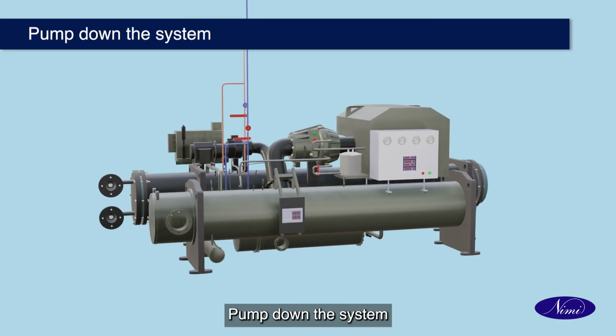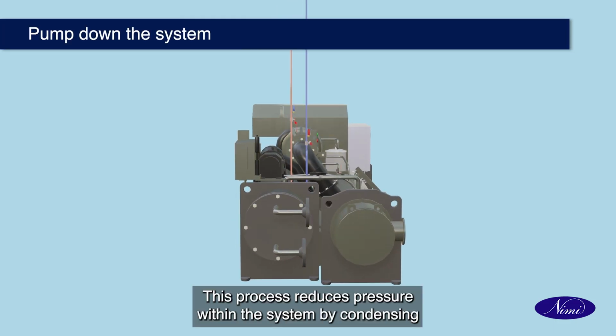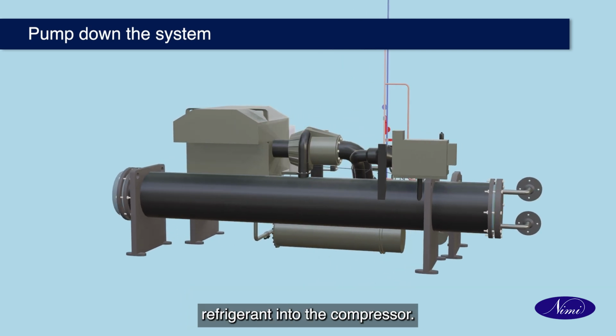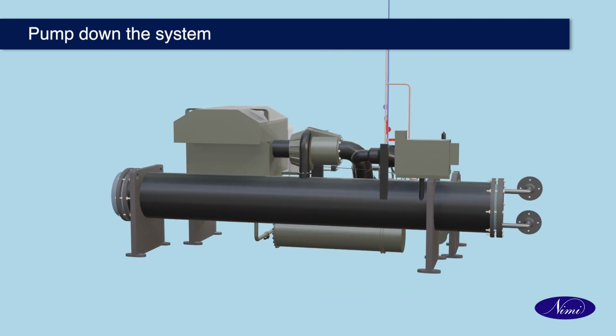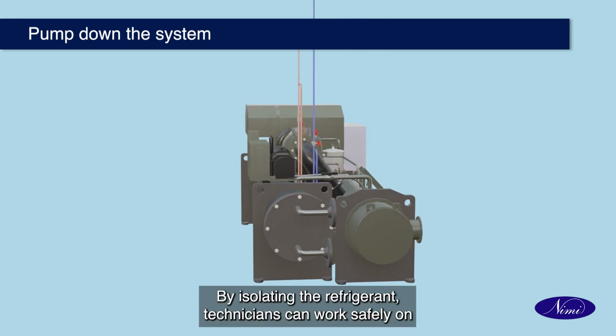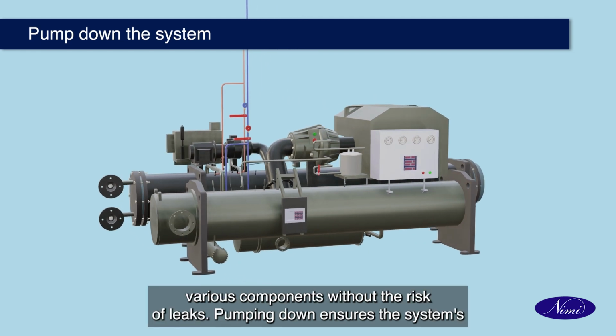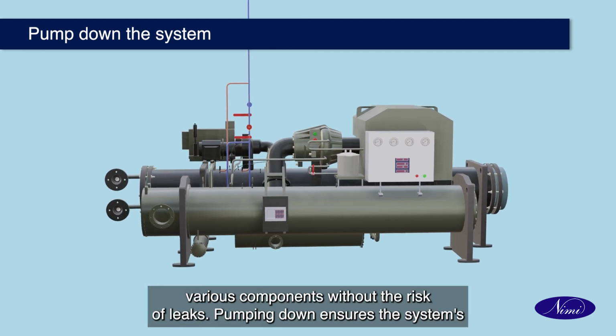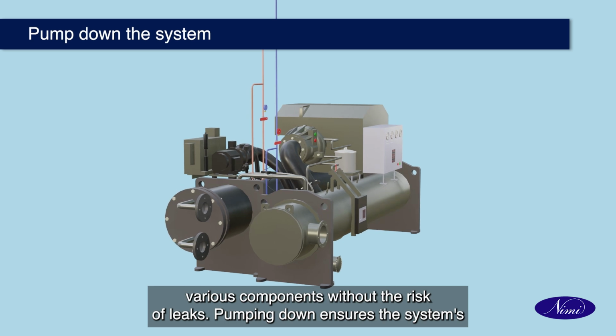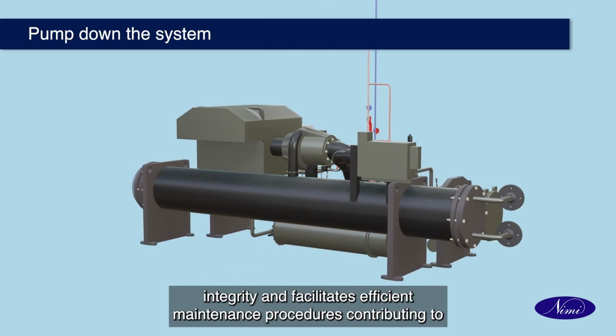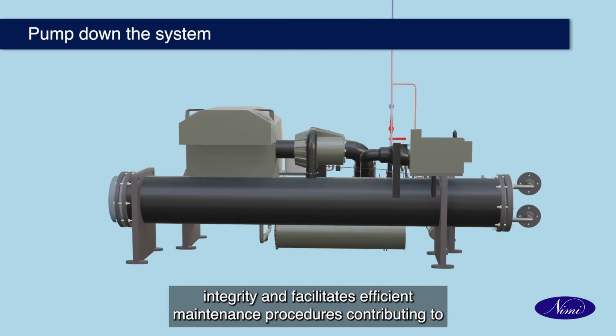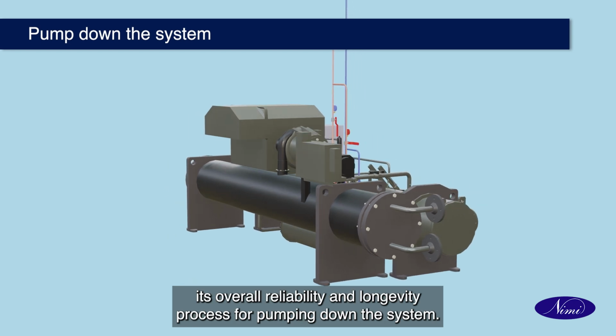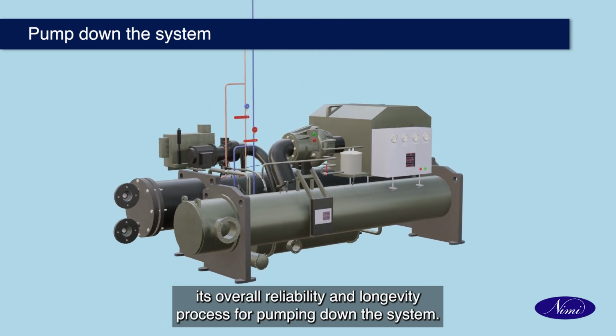Pump down the system. This process reduces pressure within the system by pumping refrigerant into the condenser. By isolating the refrigerant, technicians can work safely on various components without the risk of leaks. Pumping down ensures the system's integrity and facilitates efficient maintenance procedures, contributing to its overall reliability and longevity.